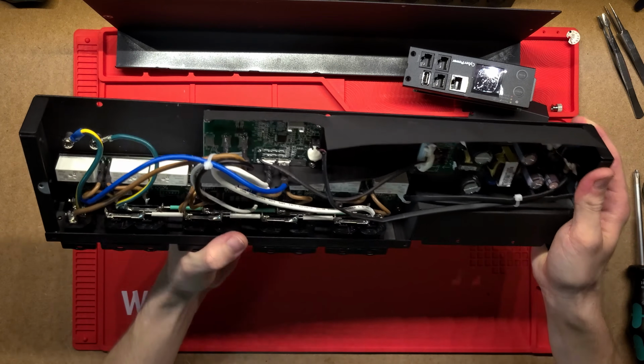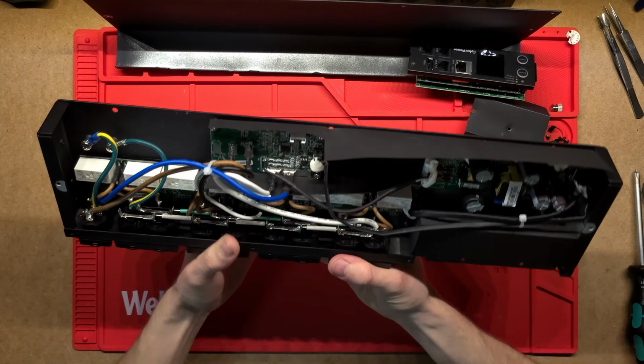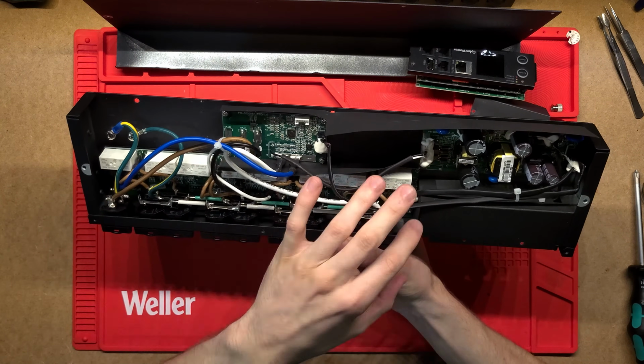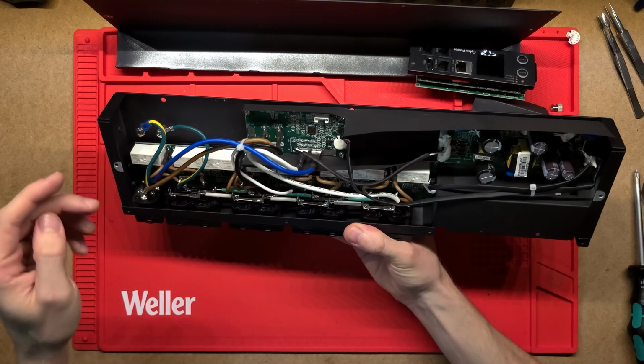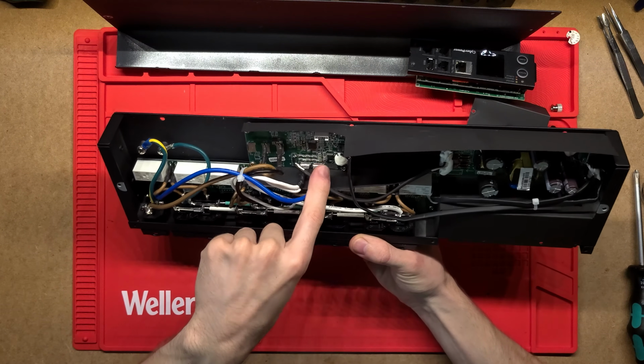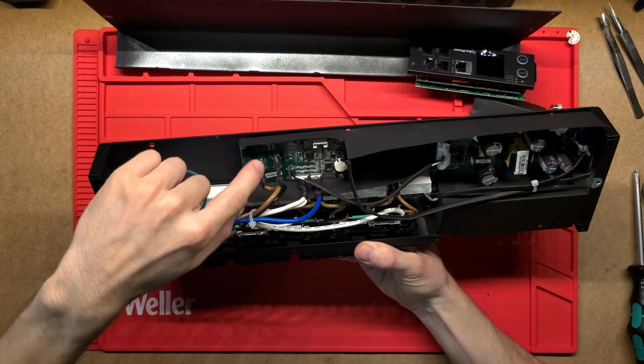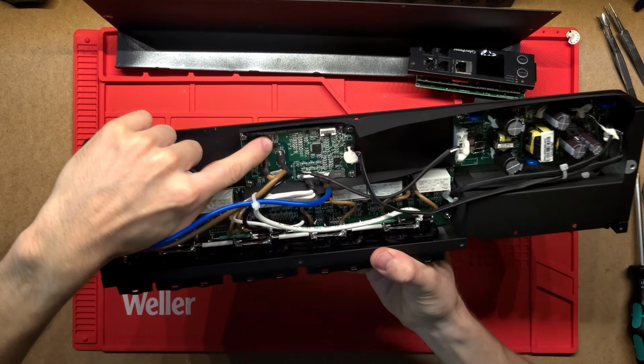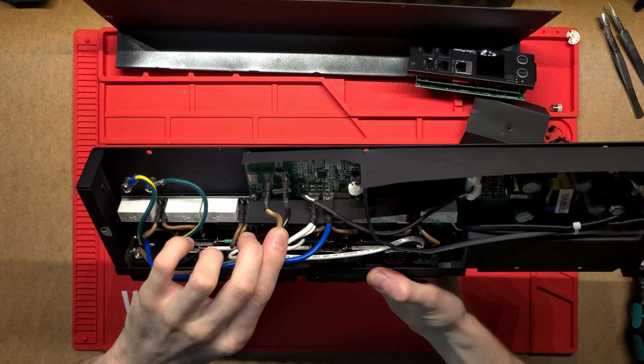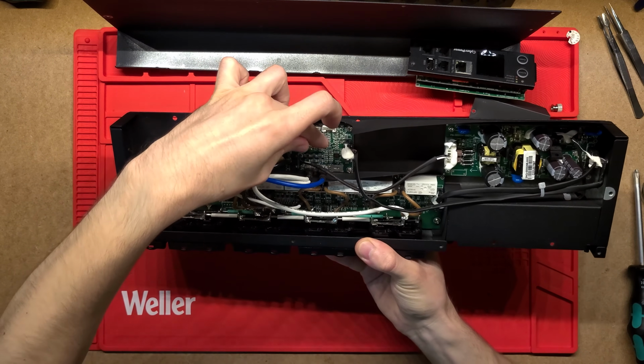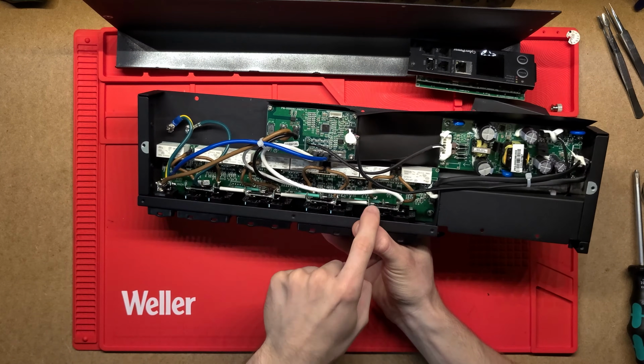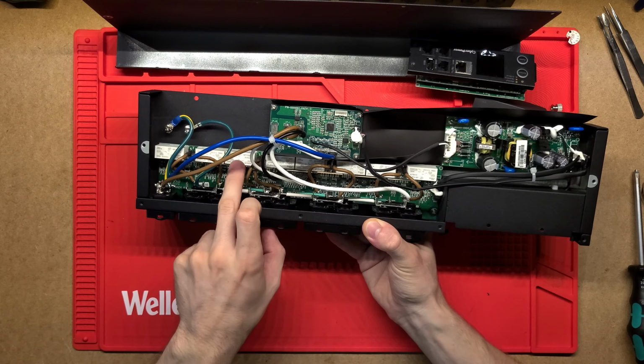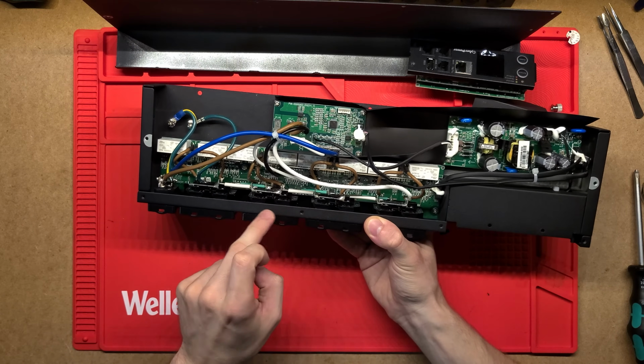What I was saying before is I don't think these are individually metered - I think I got that wrong. I think there's just one meter for the whole thing taking the measurement. So I think the power is going into this board here, and on this board we've got a little sensor that's measuring the actual current going through this. From here the high voltage goes straight onto this board with the relays, and those relays will just be turning that on and off for the individual ports.